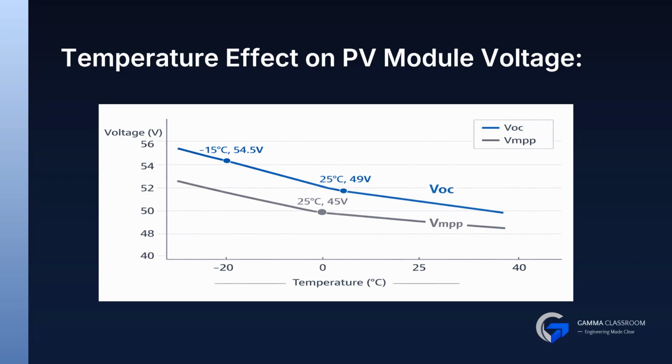We calculate open circuit voltage at cold temperature using the module's temperature coefficient. This ensures the string level does not exceed inverter limits.